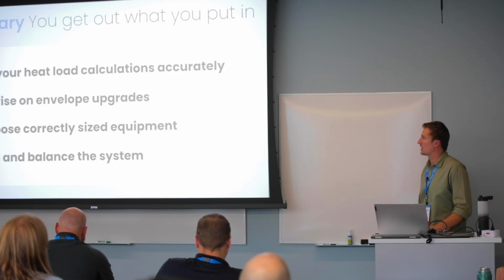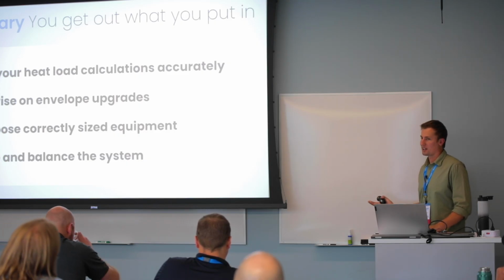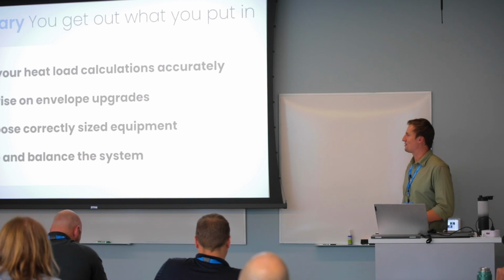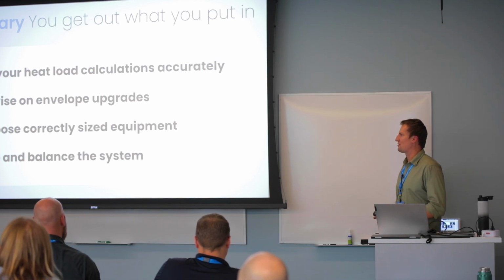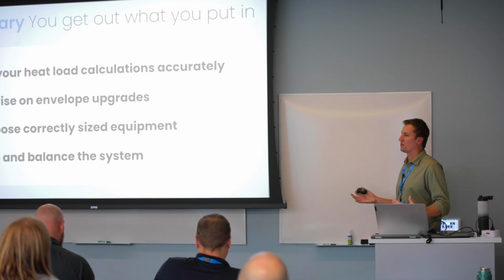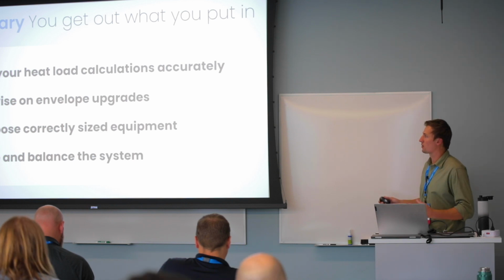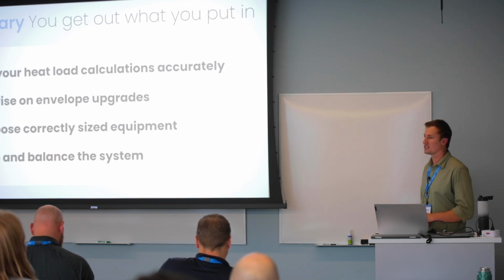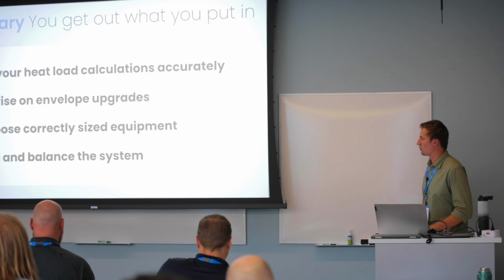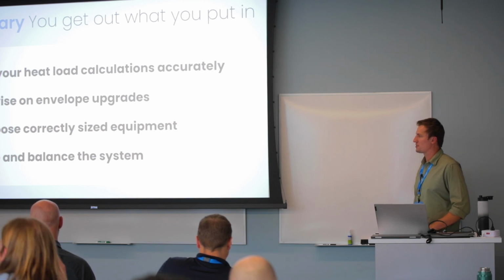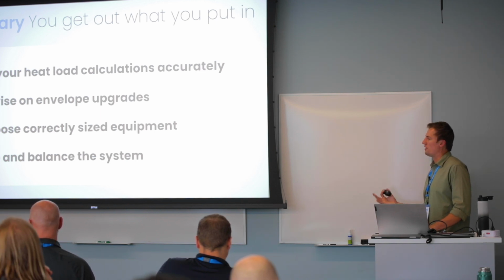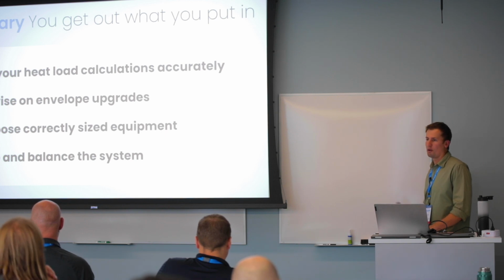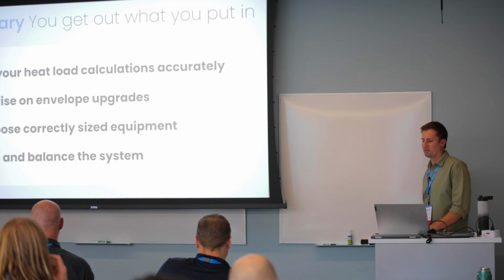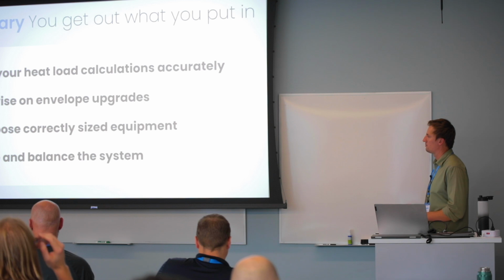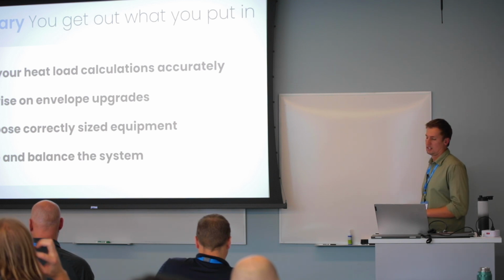To summarize the key steps: do your heat load calculations accurately, which I've said a few times. Definitely advise on envelope upgrades, and even if none are needed, letting the customer know you've checked is a good thing to do. Correctly size the equipment - no oversizing, no undersizing - and finally make sure the system is balanced and operating as designed, so flows go where you've intended them to go.